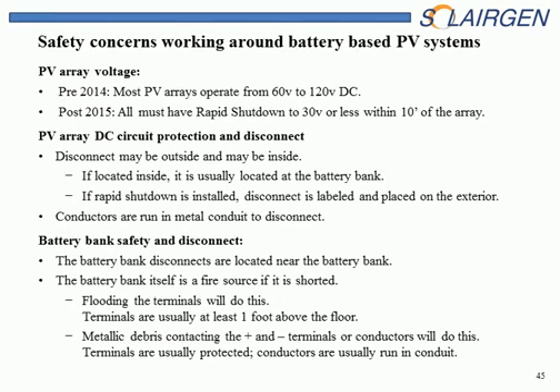And as I stated before, the battery bank safety and disconnect. The disconnect is located near the battery. The new code requires it to be within 5 feet of the battery bank. But before it was probably no more than 12, within the same room. So it's in the same room as the battery bank. And the terminals are usually high enough above the floor that there's not a shorting issue from water coming into it from trying to put out a fire. But if debris fell on exposed terminals, there could be a shorting. So there's a slight possibility there.